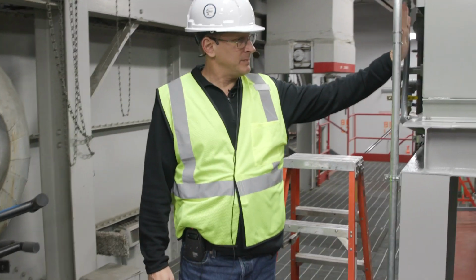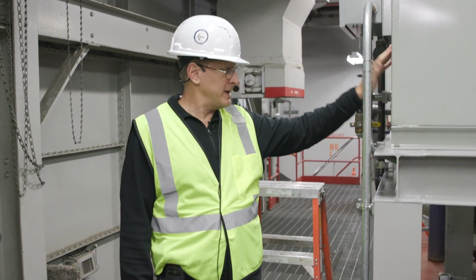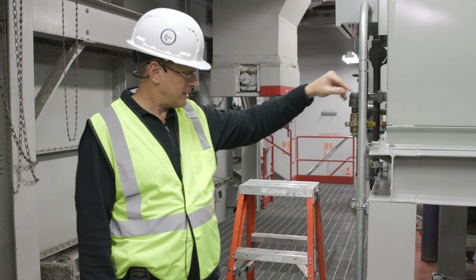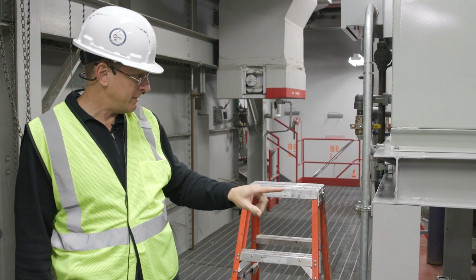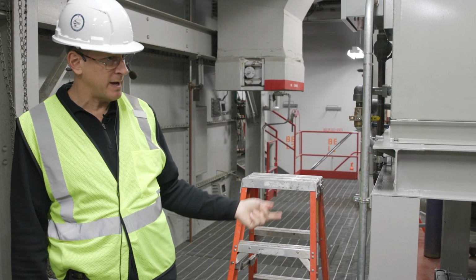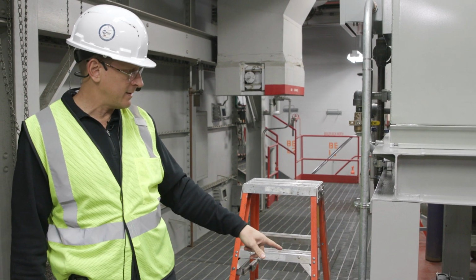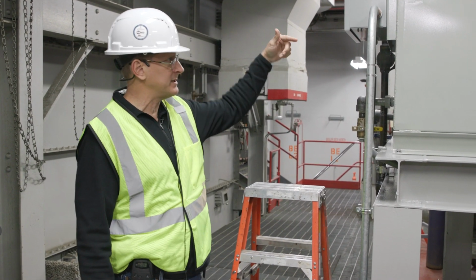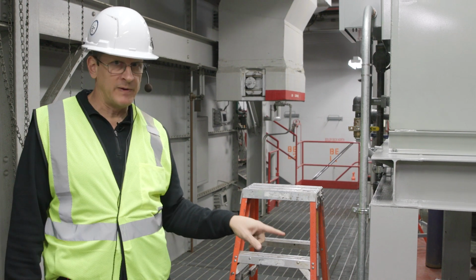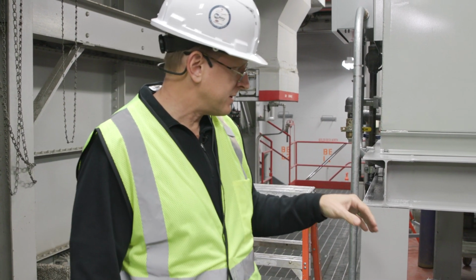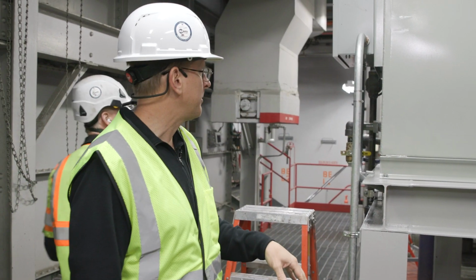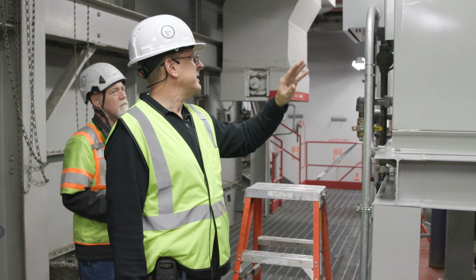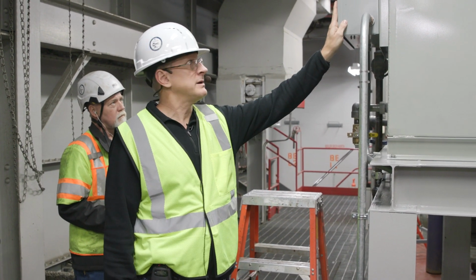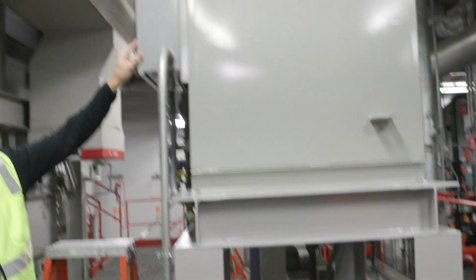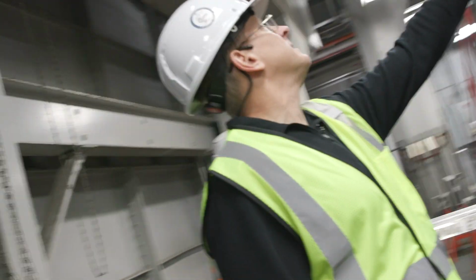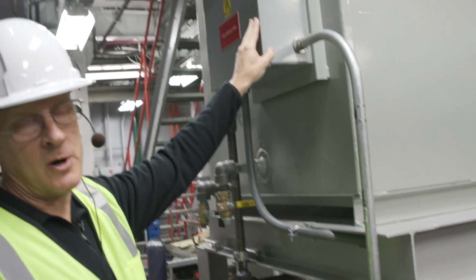Okay, this is what we call our day tank. Of course, it is raised for that gravity feed. Notice pipes coming in and out of the tank. One supplied to the engine and returned back from the engine into the fuel cooler, back into the tank. With isolation valves, again, make sure the valves are open in regular operation. We have our fuel control panel here. Light indications for letting you know various alarms or status of call for fuel, for example.